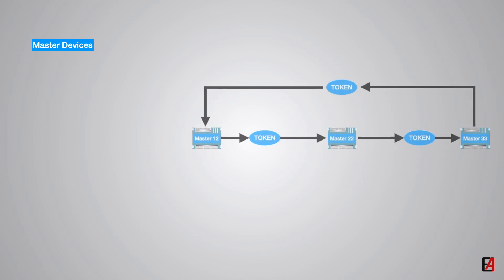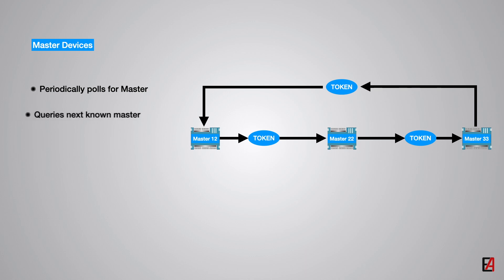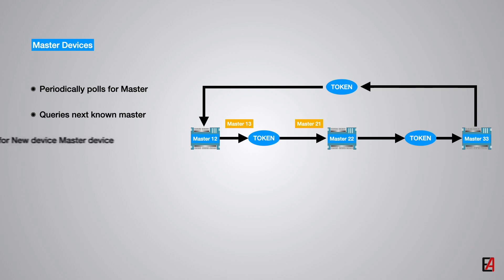Each master device on the network periodically outputs a poll for the next master. It checks its next master device's ability to forward the token. Each master device sends out a query between the own address and the next known address. For example, if the current address of the master device is 12 and the next known master device address is 22, the addresses 13 to 21 are polled periodically in ascending order to see whether a new master device was added to the network. Note that unused gaps in addresses should be avoided since this would negatively impact the performance of a BACnet MSTP system.